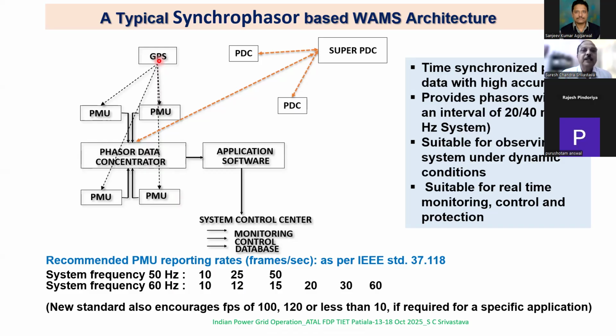The reference phasor, which is the same at every place in the electrical network, is used, and with respect to that the phase angles are calculated. Then we run various software. Now, this can give you a phasor at this frame rate. Suppose I go for 50 frames per second. That means every cycle, 20 milliseconds, I'm getting one phasor.